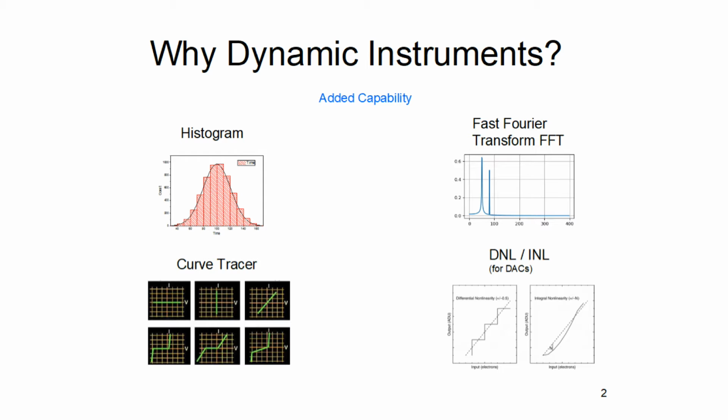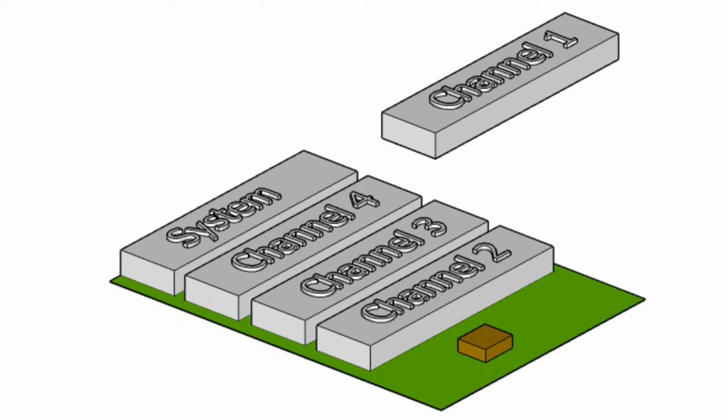We will demonstrate these capabilities in this demo of the Milliohmmeter, which is part of the MCX Modular Dynamic Meter. The MCX architecture consists of single-channel dynamic instruments mounted onto a motherboard. We can configure the MCX in any number of channels with any of our dynamic instruments.